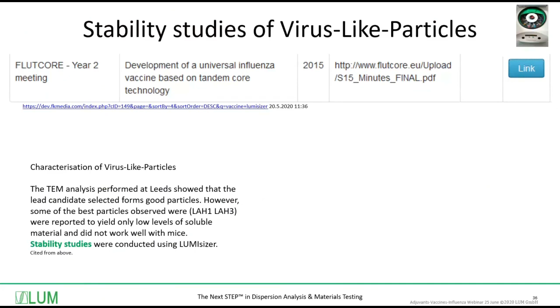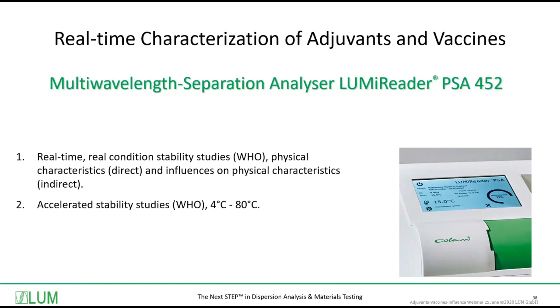Once we talk about the real-time characterization of adjuvants and vaccines, we always talk about the multi-wavelength separation analyzer, LUMiReader PSA, now in the most modern version 452. We can perform the real-time, real-condition stability studies according to the WHO, here with a focus on the physical characteristics directly, and we indirectly characterize other characteristics if those have an influence on the physical behavior. We also can perform accelerated studies according to WHO because we have a temperature range in the instrument from +4 Celsius up to +80 Celsius.